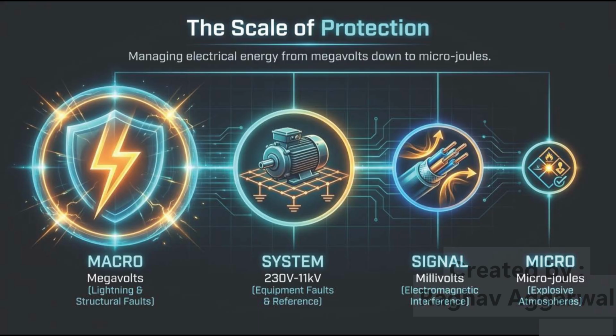Before looking at each protection method individually, it is helpful to understand the different scales of electrical energy that exist in a plant. This slide shows 4 levels of protection. At the macro level, we deal with megavolt energy sources such as lightning and major structural faults. These events are rare, but they can be extremely destructive. At the system level, we see normal power distribution systems operating between approximately 230 volts and 11 kilovolts. Here, the main concern is equipment faults and maintaining a stable electrical reference.